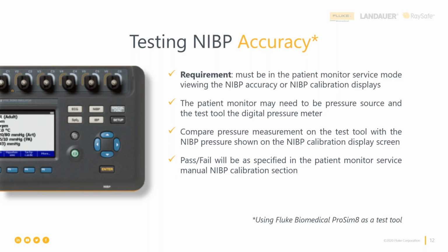Well, how can you do it then? Well, you need to have the service manual for that medical device, that blood pressure device, and you need to look in there in the testing and the calibration procedure for NIBP, and that is where you have the controls of that medical device to close the relief valve so that you can pressurize the system and hold it at a specific pressure level. And if you can't hold it at a pressure level, that tells you something else. It failed the test, and now the troubleshooting happens. You say, why did I have such a big leak when I sealed the relief valve? So we go from measurement and calibration to it failed, now I have to do a corrective action.